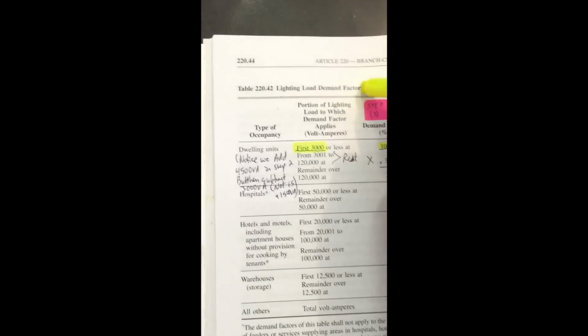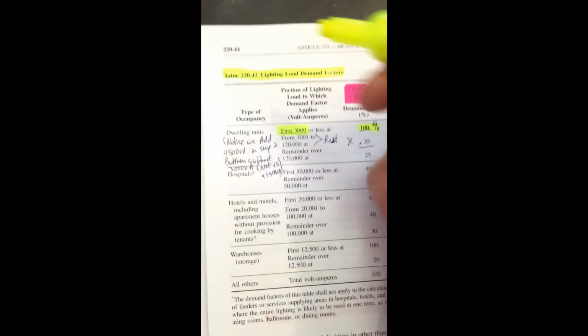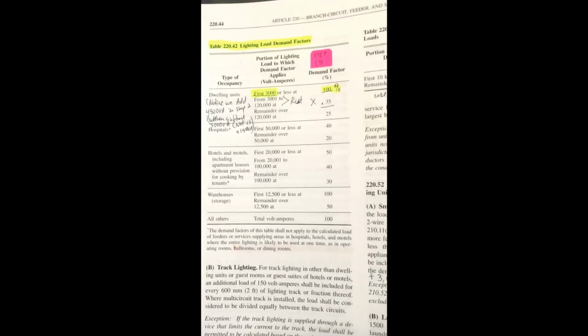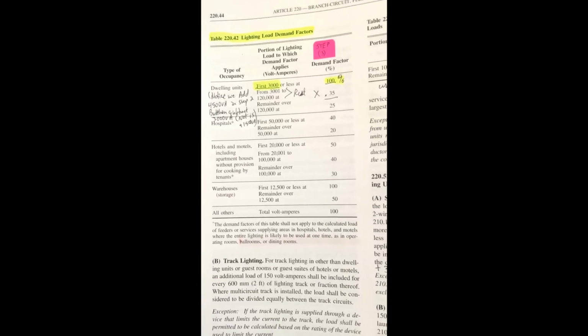And this is the lighting loads. This is basically step two, if you like. Step one being the 3 volt amps per square foot. Step two being the derating for the lighting. And in the case of dwelling units, receptacles as well, right?